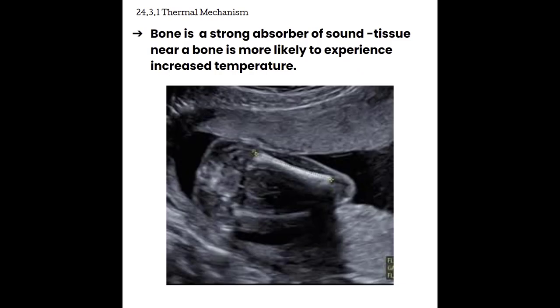We know that bone is a very strong absorber of sound. So tissue near bone is more likely to experience increased temperature. And we are particularly concerned about this with fetuses. Fetal tissue is more likely to experience temperature changes. Therefore, the thermal indices need to be carefully observed during fetal ultrasound. In this image here, we can see the femur of a fetus. It is the tissue around this femur, especially as this bone calcifies and hardens during gestation. The tissue around this is more likely to heat up because of this bone absorbing ultrasound energy.